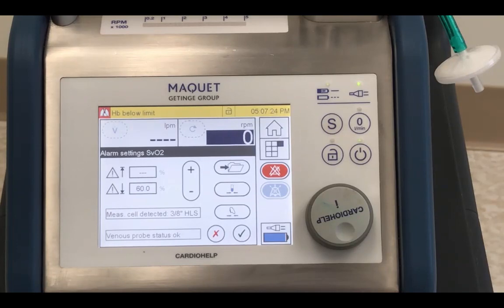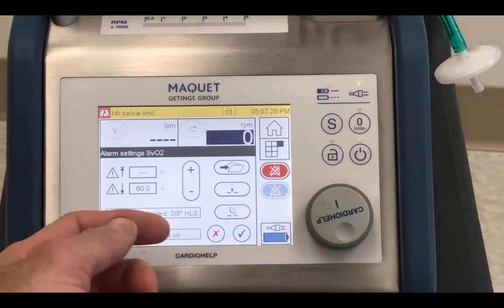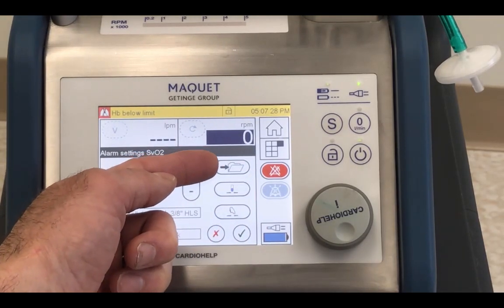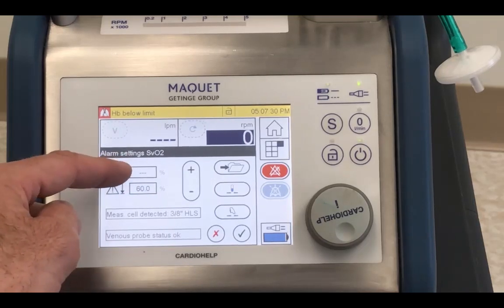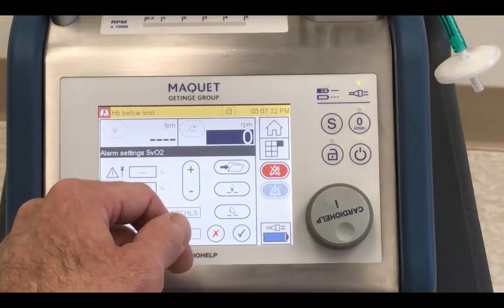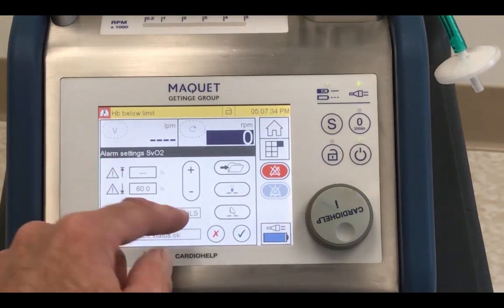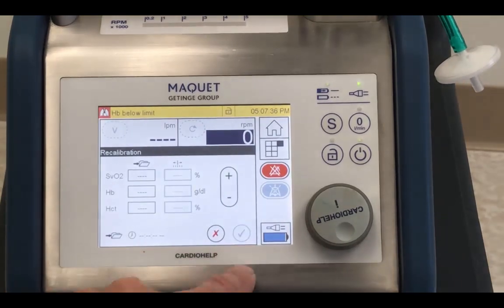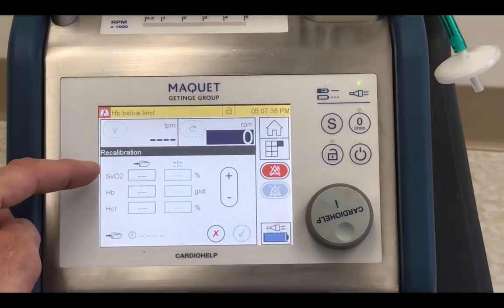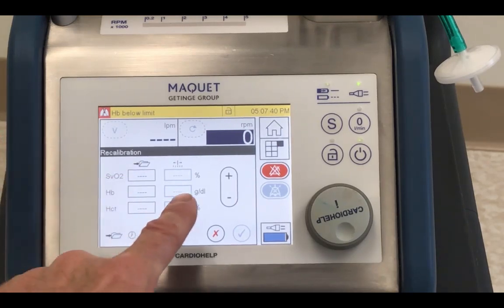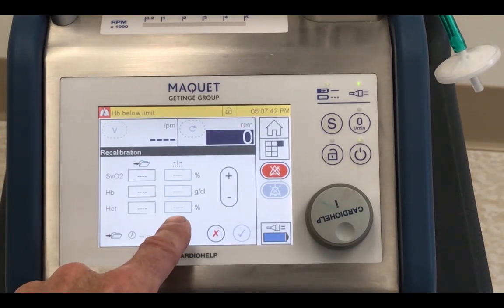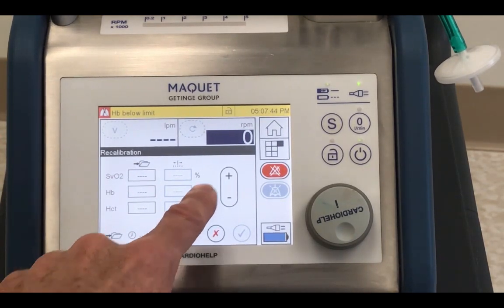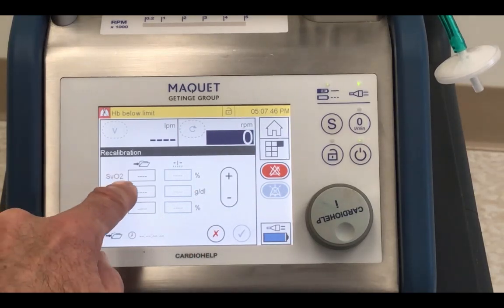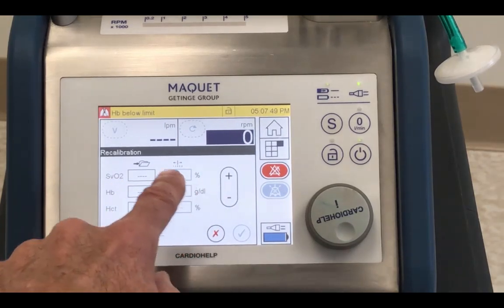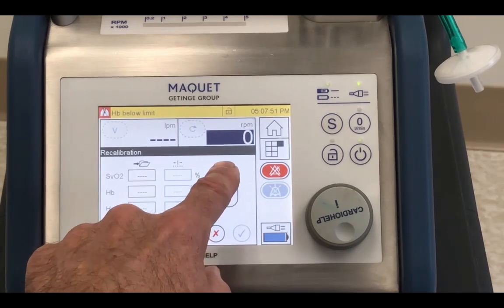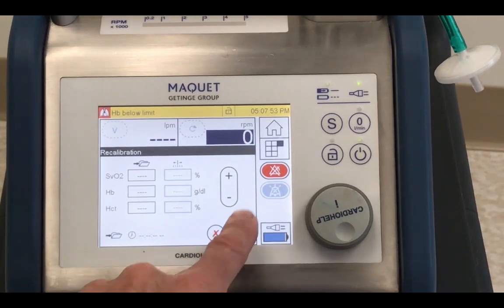Another thing you can do from your SVO2 screen here is enter data. You can save the data you're reading from your SVO2, put it into a folder, and then when it comes back, you can recall that data. You press that button, and it will tell you the data that's in the file, and you would change it to the data you're getting back from the laboratory with your arrow buttons. If there's a 70 over here and it's supposed to be 72, you would tap that and move that around to 72, and then enter that data.